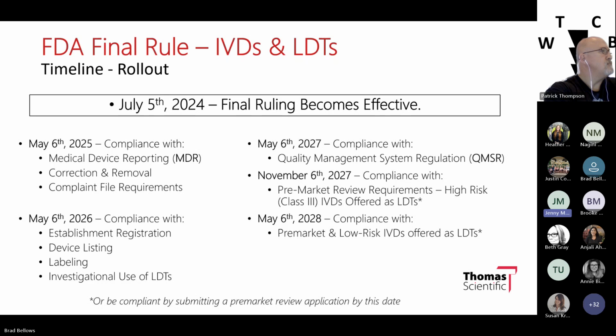May 6, 2026, compliance is expected with establishment registration, listing your LDT or your IVD device, labeling, and investigational use of LDTs. May 6, 2027, quality management system regulation compliance is expected. On November 6, 2027, there should be compliance with pre-market review requirements for high risk, that would be the class 3 IVDs offered as LDTs.